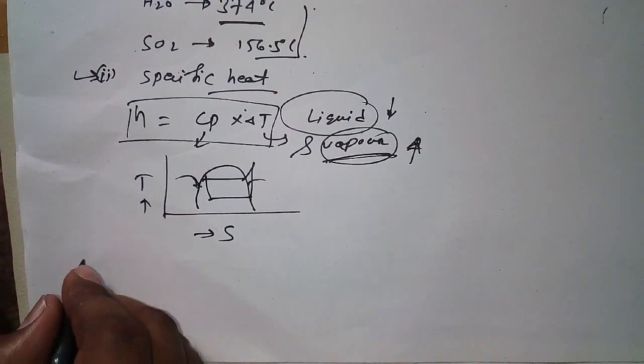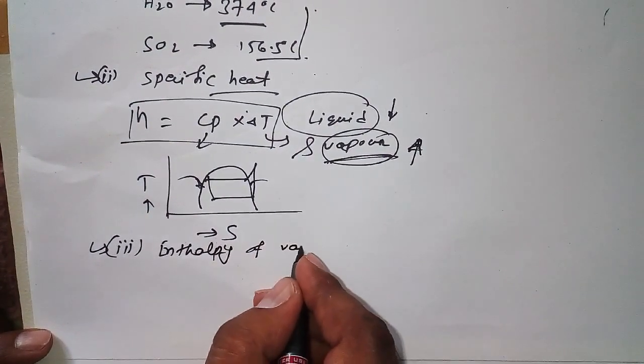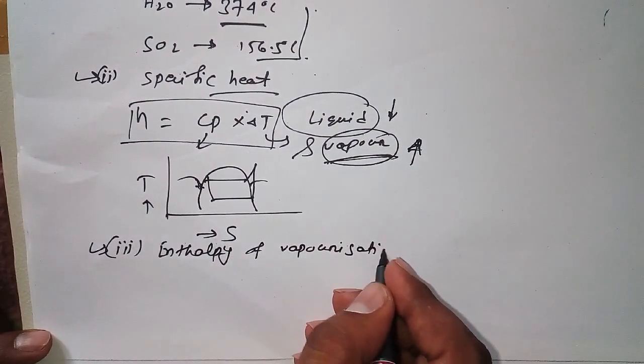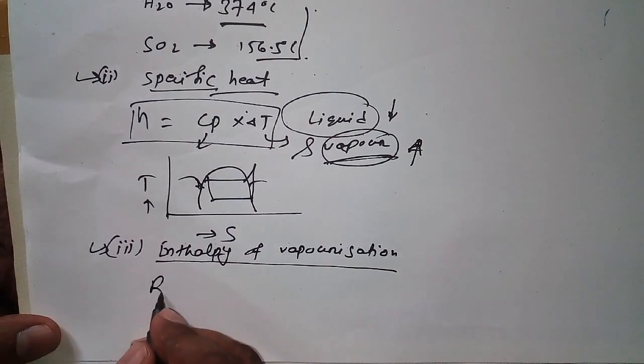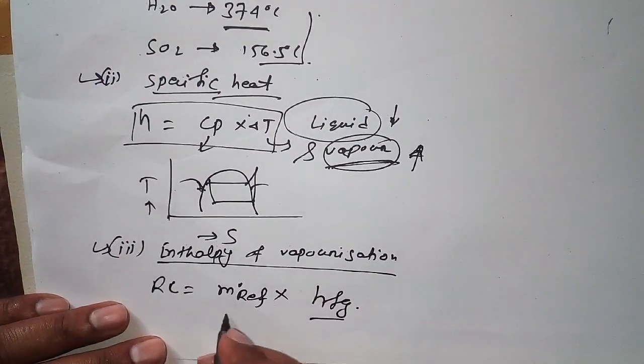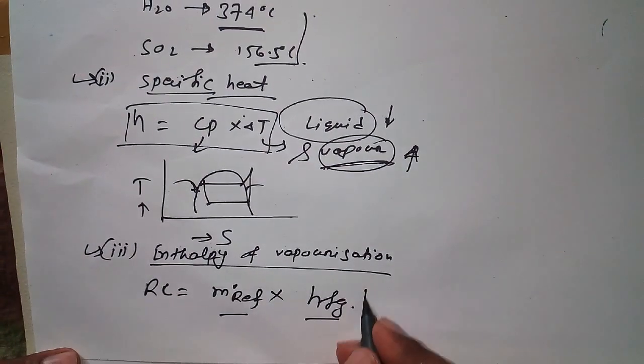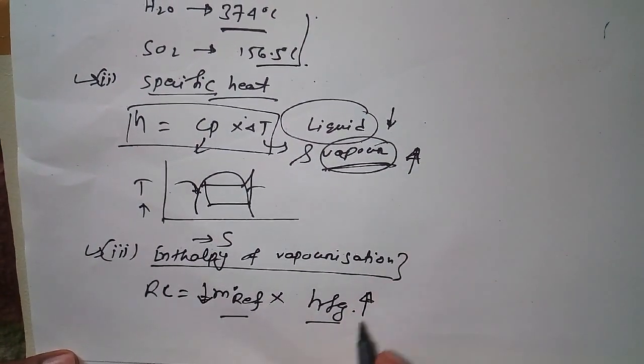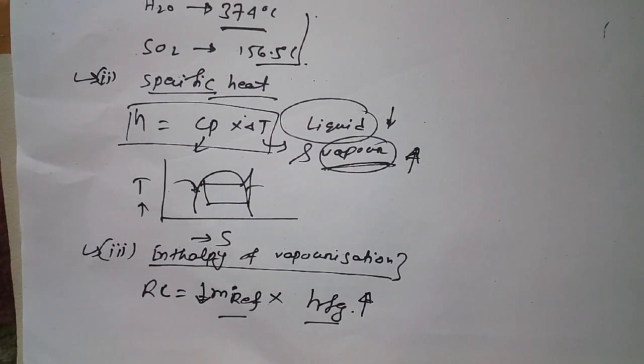Now moving to the next thermodynamic property — enthalpy of vaporization. Enthalpy of vaporization should be as high as possible, because a higher value requires a smaller mass flow rate of refrigerant for the same capacity. Refrigerant capacity equals mass flow rate of refrigerant multiplied by hfg. If hfg is higher, the required mass flow rate (kg/s) will be lower.